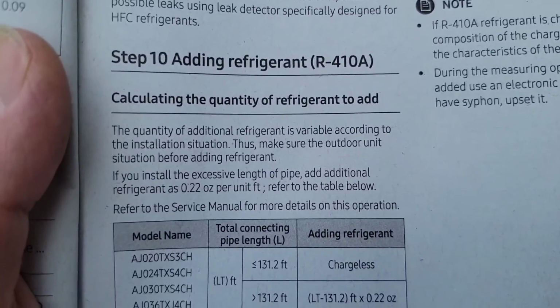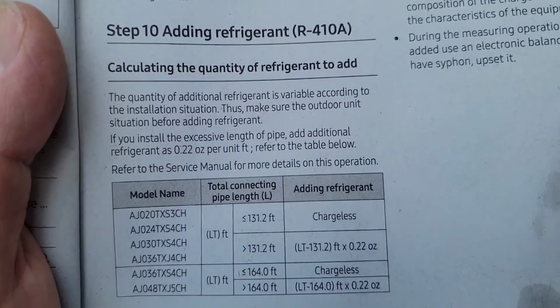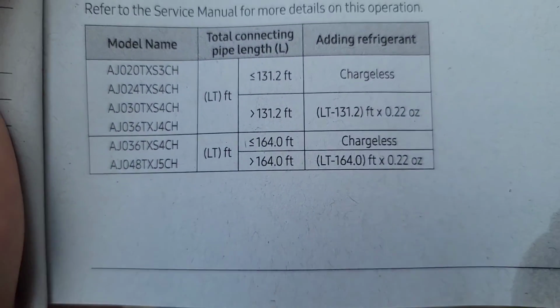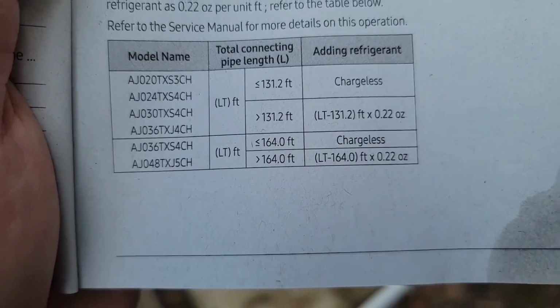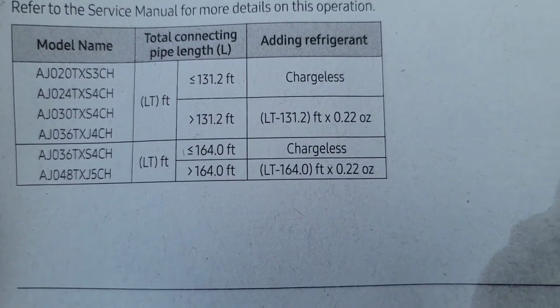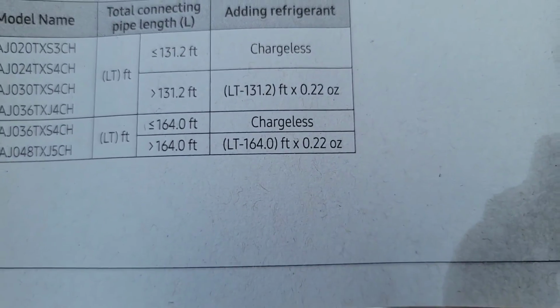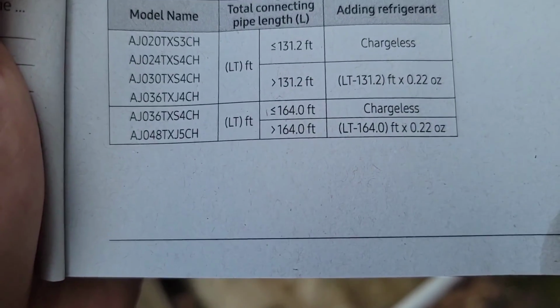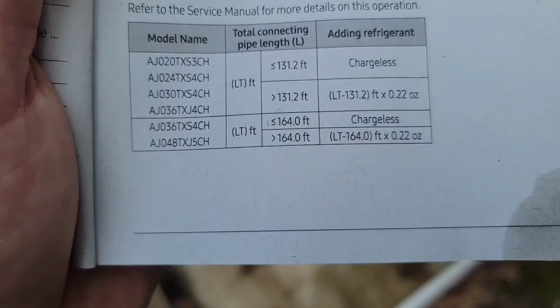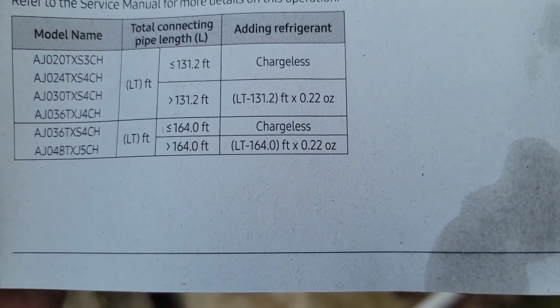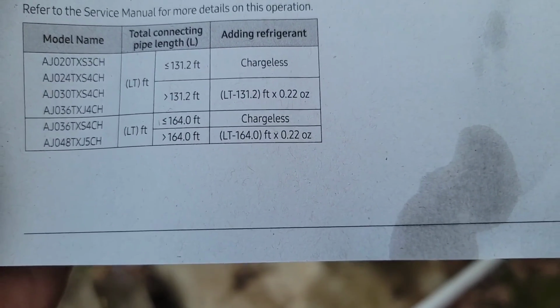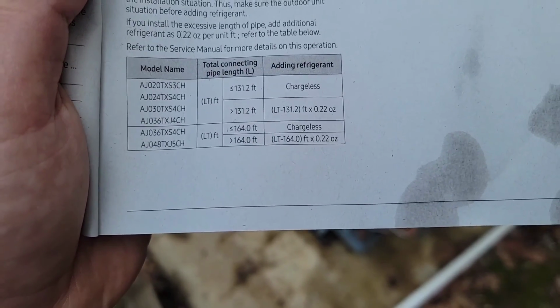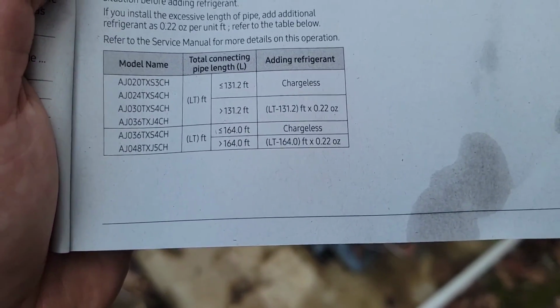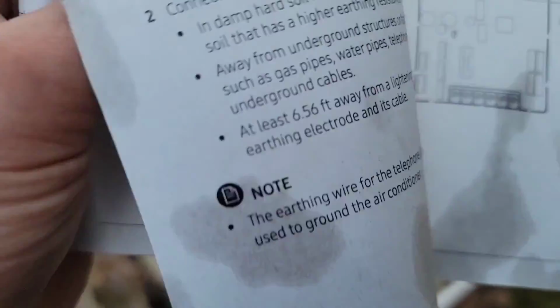Now, in the installation manual under adding refrigerant, calculating the quantity of refrigerant to add, if we have less than 164 feet of line set length, then we don't have to add any refrigerant. See, it says chargeless. After 164 feet, so more than 164 feet, we multiply per foot by 0.22. So say we had 200 foot of line set. That means 36 feet times 0.22. Hopefully I'm doing that correctly.